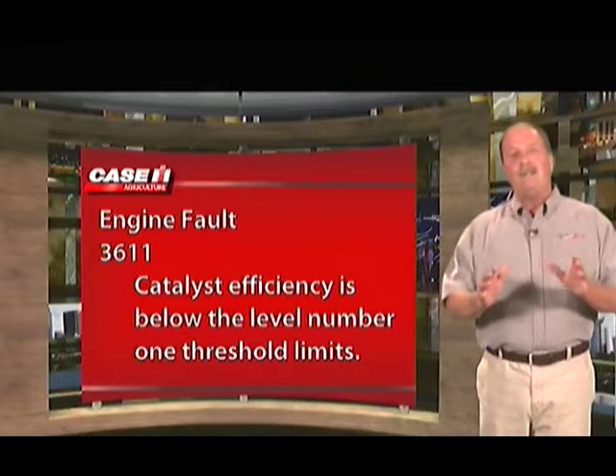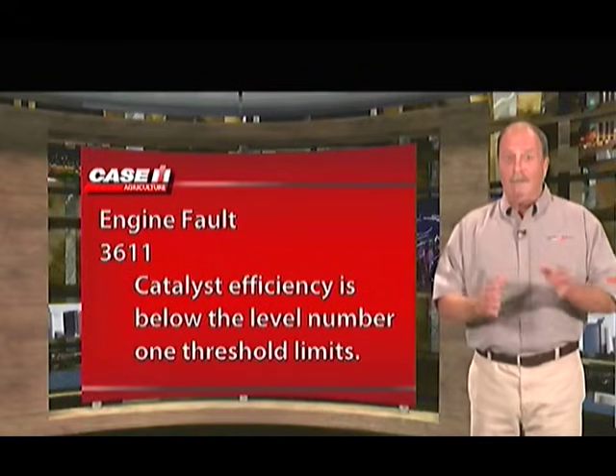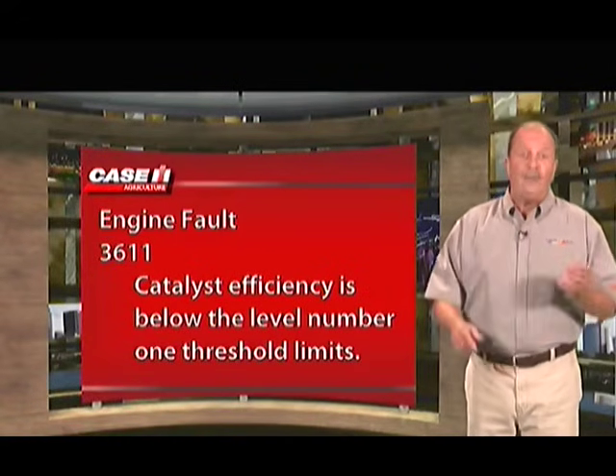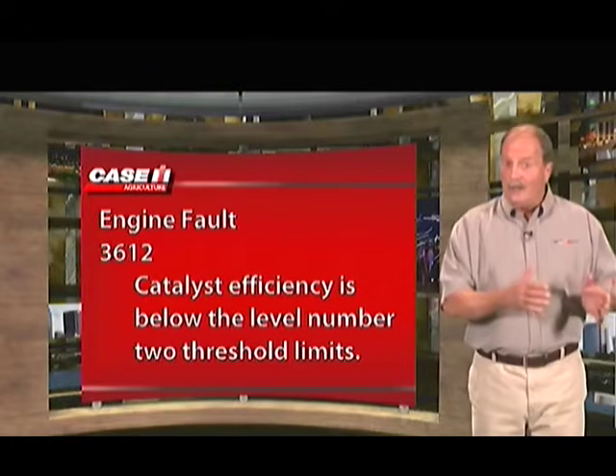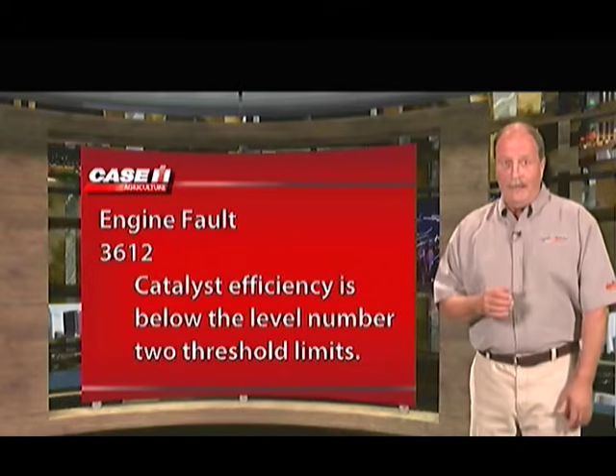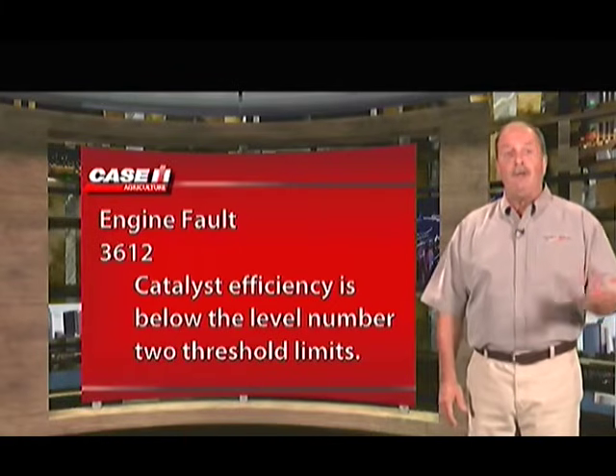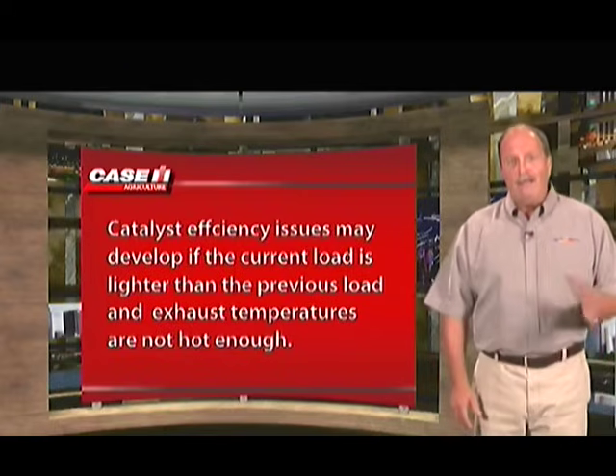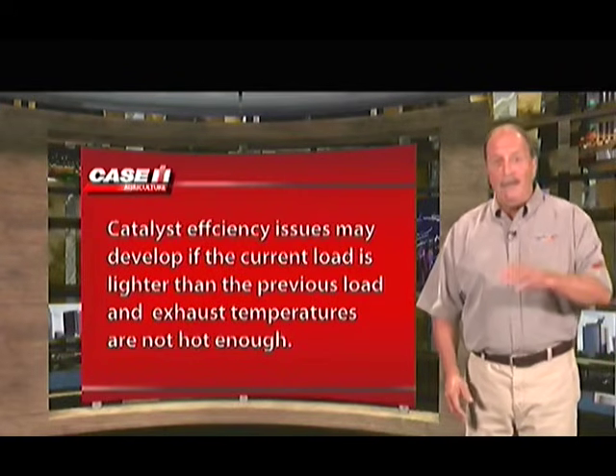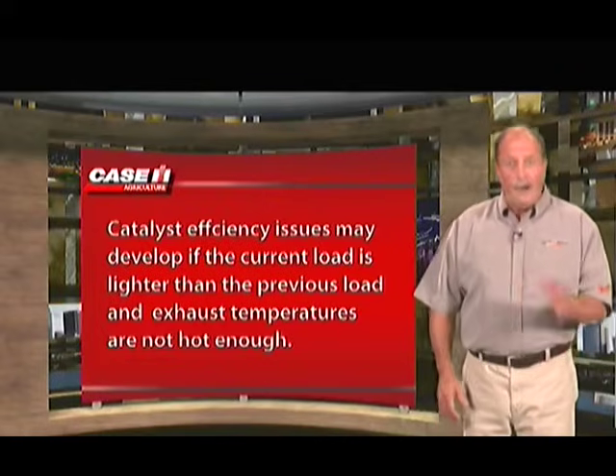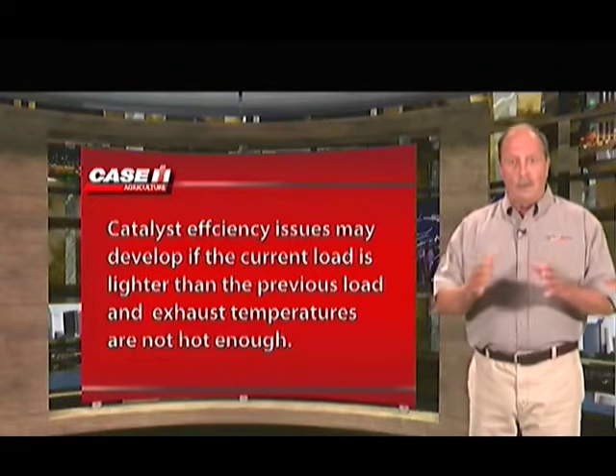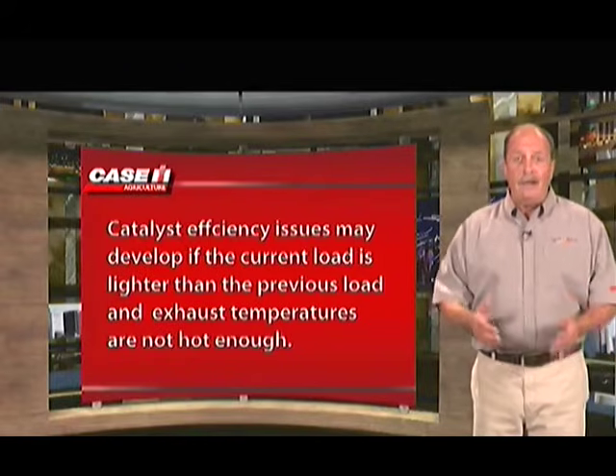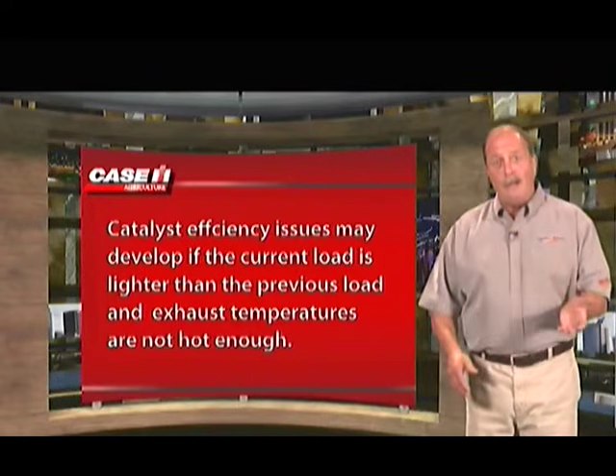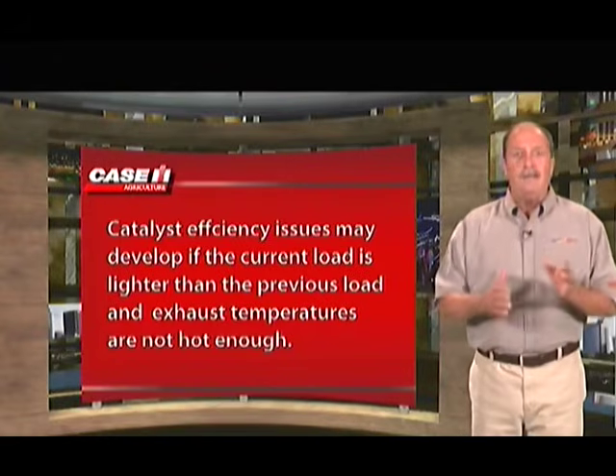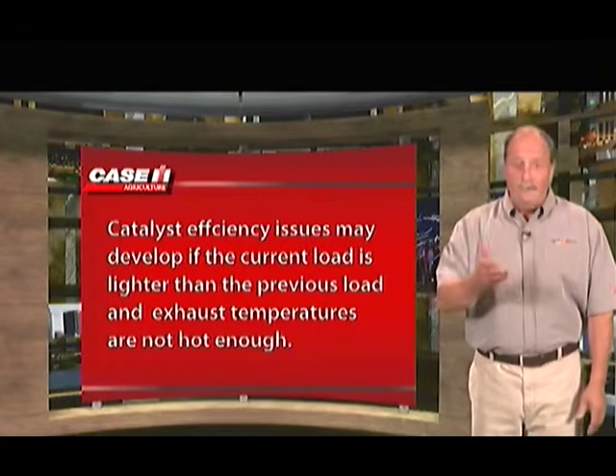Engine fault 3611 indicates the catalyst efficiency is below level number 1 threshold limits. Engine fault 3612 may follow 3611 and indicates catalyst efficiency is below the level number 2 threshold limits. Catalyst efficiency issues may develop if the current load is lighter than the previous load and exhaust temperatures are not hot enough. As the catalyst cools down, the efficiency drops because heat is a primary factor in nitrogen oxide conversion. This decrease in performance can indicate an efficiency fault.